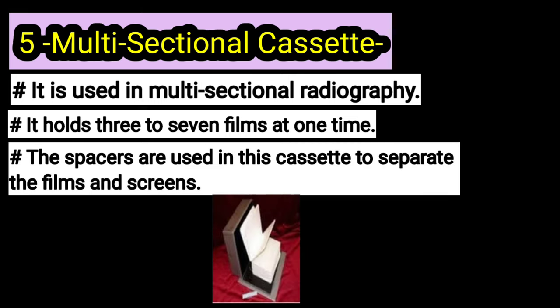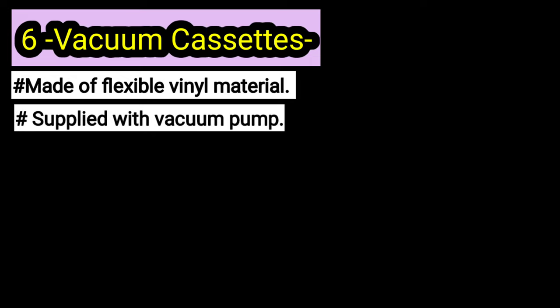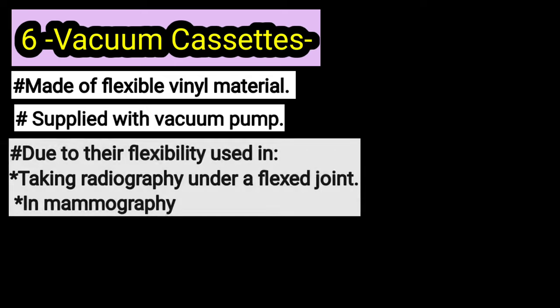Spacers are used between the films. After that are vacuum cassettes, which are flexible cassettes. The film has to be loaded under vacuum, and after loading, the vacuum is released so that good screen-to-film contact is achieved. These were also used for curved body parts.